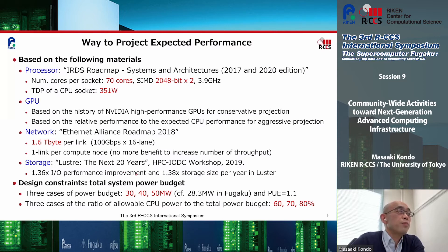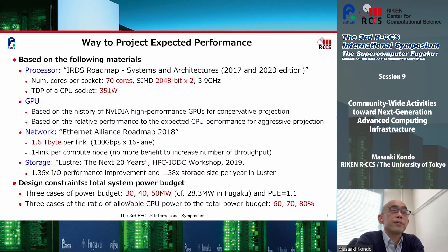An important design constraint is total system power budget. We assume three cases of total system power budget — 30, 40, and 50 MW — with a PUE of 1.1. We also assume three cases of the ratio of allowable CPU power budget to total power budget: 60%, 70%, and 80%.